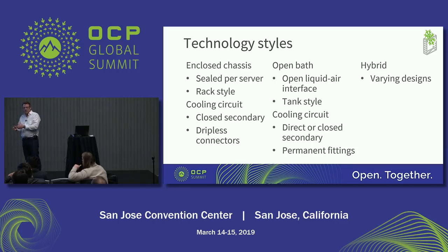The strategy is, in some cases, also overlapping with cold plate challenges. Open bath is a fundamentally different approach. The term open, as I mentioned before, refers to the air interface to the liquid being open. So there's surface tension between the liquid and air. So by definition, an open bath structure is tank style. So it's got a tank, there's multiple servers in the same tank. If you're only doing one server per tank, then you would most likely seal it and put it in a rack. And then you get back to the enclosed chassis.